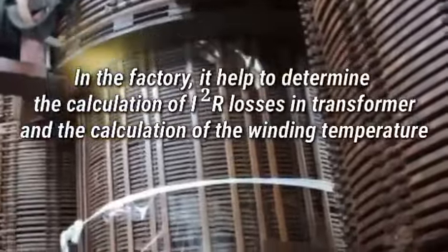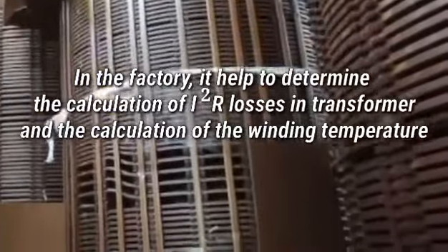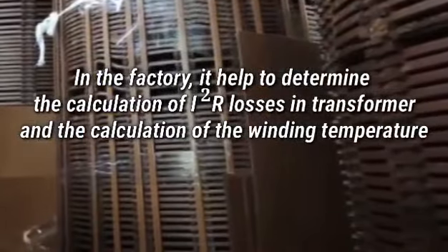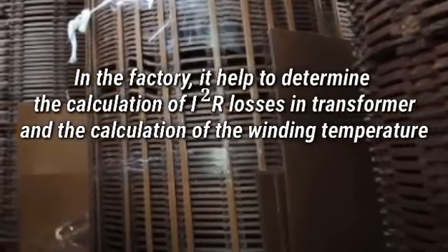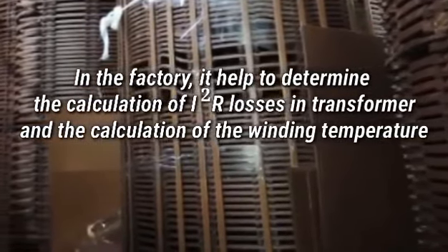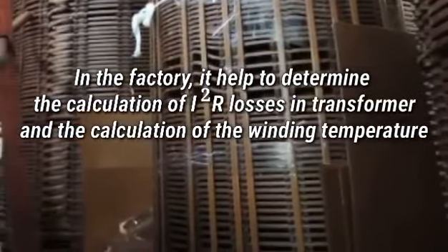In the factory, it helps in determining the following. First, the calculation of the I2R losses in the transformer. And secondly, the calculation of winding temperature at the end of the temperature rise test of the transformer. These are our base for assessing possible damage in the field. Talking about the I2R losses in a power transformer.